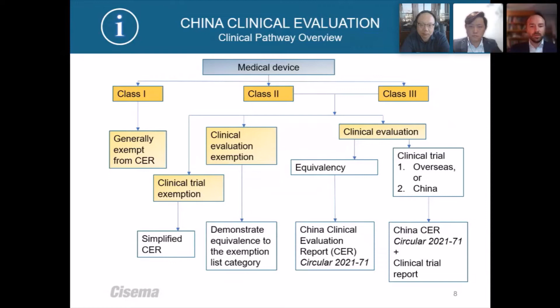So going into a bit more detail here, as we set out, the class 1 product is relatively straightforward. It submits an exempt CER. Class 2 and 3, the first question is really, is the product on the clinical trial exemption list? If the answer is yes, then it's straightforward. The simplified clinical evaluation report will be sufficient. If it's not, then you ask, is it CER exempt? This, as I mentioned, is a relatively new requirement. If it is on the CER exemption list, then it's also straightforward. You don't need to provide a CER. If it's not, then we go into a more detailed analysis, which we're going to dive into in a moment.